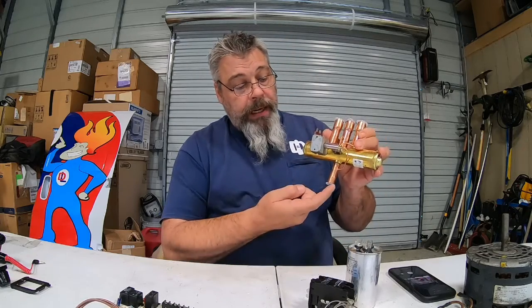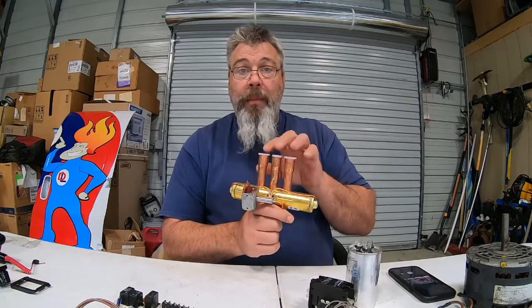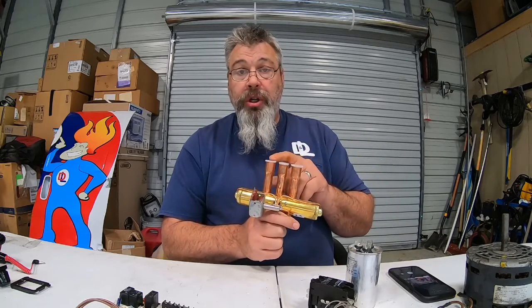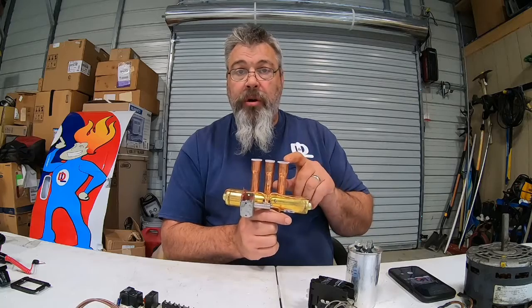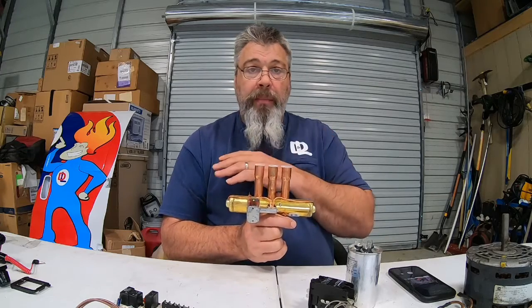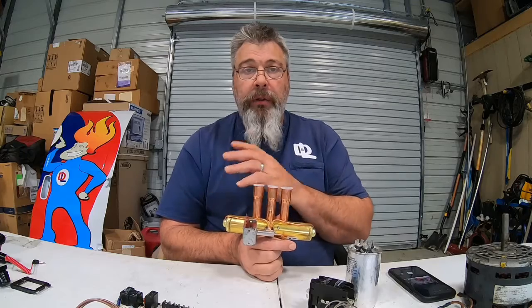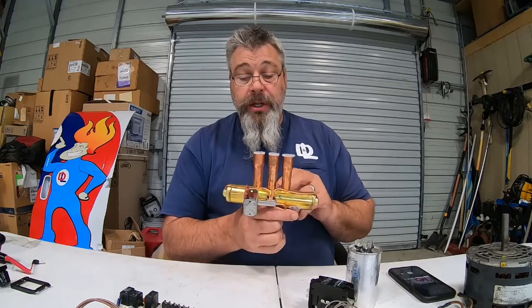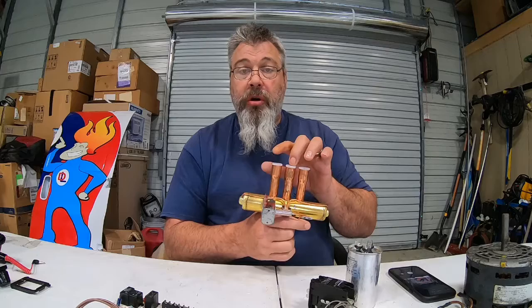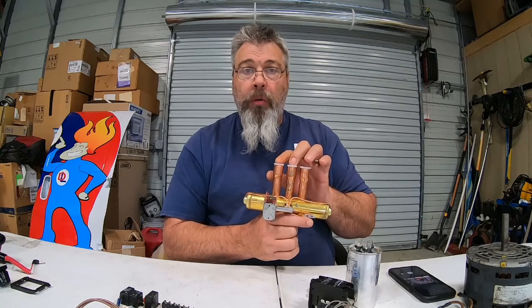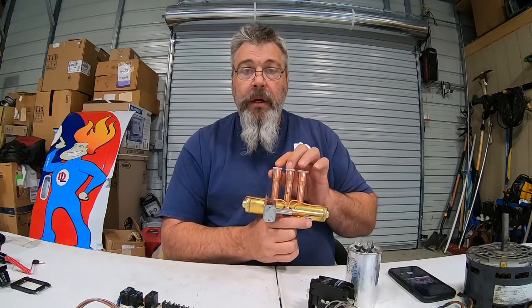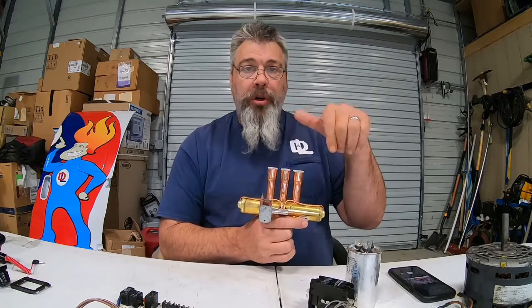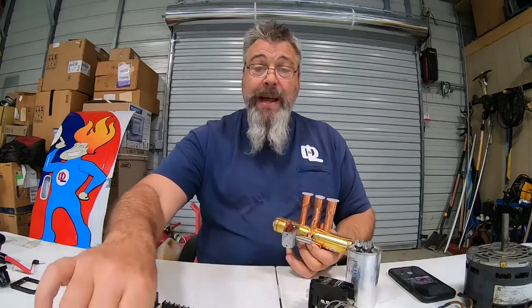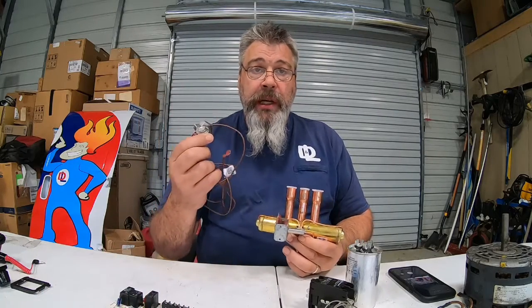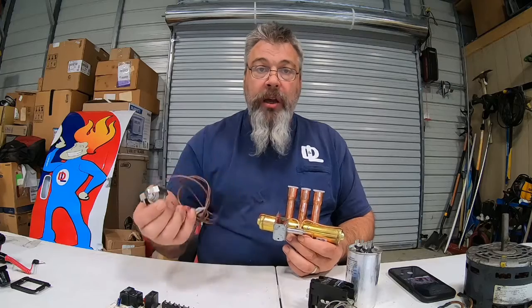When we have refrigerant coming in, we have three ways to come out the top of this. One goes to your compressor, one goes to your condenser, and one goes to your evaporator. We'll talk about the evaporator later, because that'll be in a different air handler inside. But what we'll do is bring this in and allow the compressor and the condensing coil to get hot gas. And what that does is it defrosts the coil on the outside. It'll defrost it until that sensor reads the ohms of resistance it needs to de-energize defrost mode.